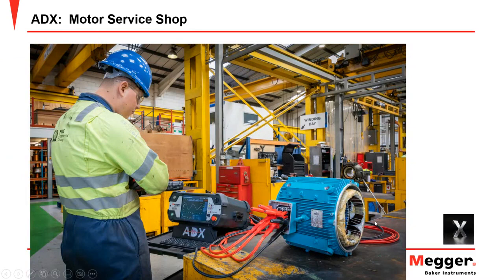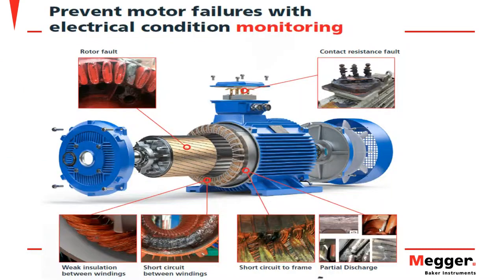The connections in the motor itself: this is a service shop. You can see a few motors that are dismantled. We don't have to have the motor dismantled. We can have the motors assembled. There are a few things with assembled motors that we have to take into consideration, such as the rotor influence. But overall, the motors can be tested exactly the same in a workshop as they can out in the field, giving us that nice trending ability to be able to spot any problems ahead of time.